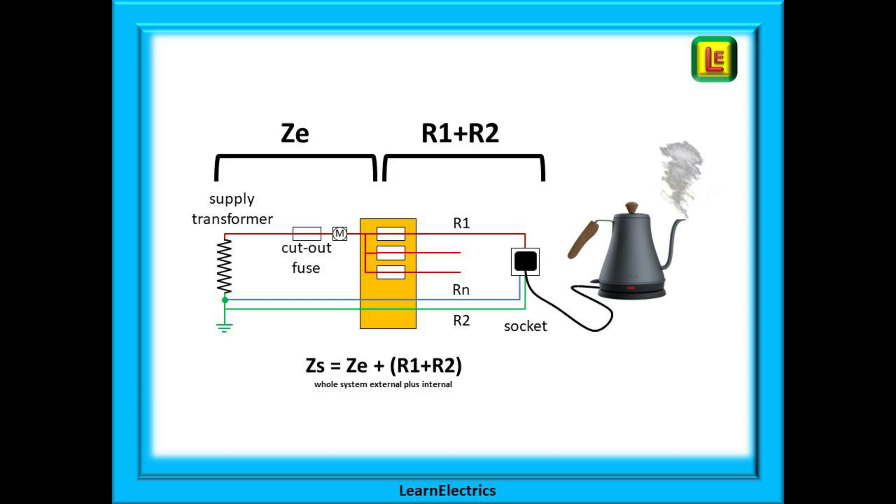ZS is the impedance or resistance of the whole installation, that is to say all of the outside wiring from the consumer unit back to the supply transformer and all of the inside wiring from the consumer unit to the point of use. It uses the formula shown here: ZS equals ZE plus R1 plus R2. And we have divided our drawing into two to show this. ZE is everything on the left before the consumer unit, and R1 plus R2 is everything on the right inside the building after the consumer unit.